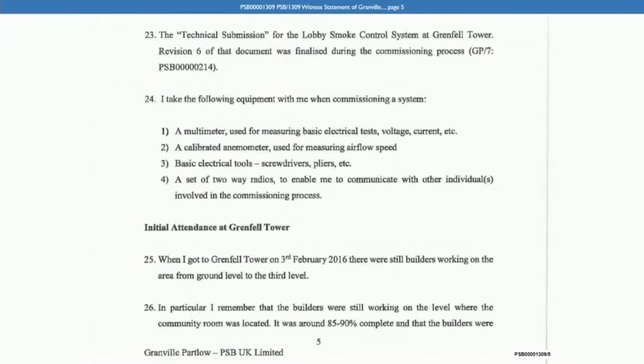Now, if we look at paragraph 24 of your first witness statement on page 5, here we can see that when you commission a system, you take with you a multimeter for measuring basic electrical tests, voltage, etc., a calibrated anemometer used for measuring airflow speed, basic electrical tools, a set of two-way radios. Do you take a calibrated device for taking pressure differential readings with you? Not on the first visits, no, because we wouldn't have anything set up to measure at that point. Probably from the second visit, and maybe even the final visit. Well, the final visit definitely had the DPM with me.